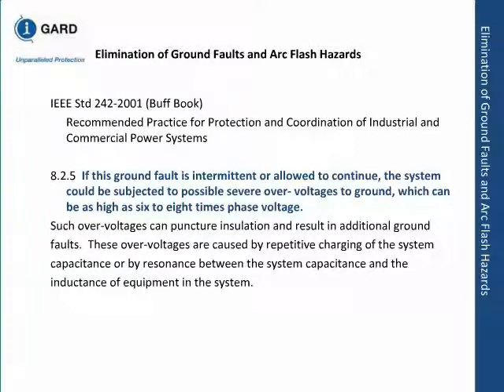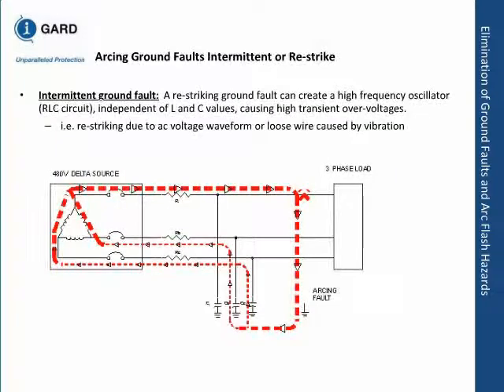Okay. You can see in this sketch that the arc will restrike on an ungrounded system and the voltage will keep building up until something else clears it. That is the reason it's so damaging. Why would industry use it? Because the first fault would not cause an interruption in the process. That was industry's goal. Another problem in the ungrounded system is you cannot have fault detection.